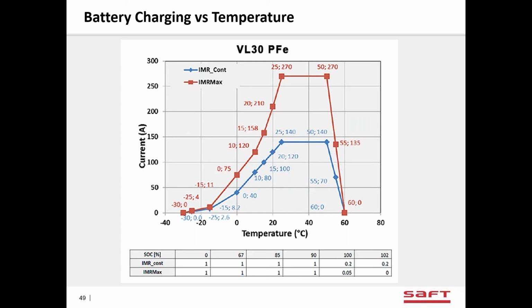If we're using a conventional charger that does not have the software built in to recharge the battery, we typically set the charge rate down low, maybe 20 amps, and that would give us a slower recharge time. But we look at the temperature requirements for the room and ask how low the current has to be to stay under this curve, and so we just set the maximum current. Typically we recharge with a conventional charger in 6 to 10 hours instead of recharging in maybe a little over an hour.